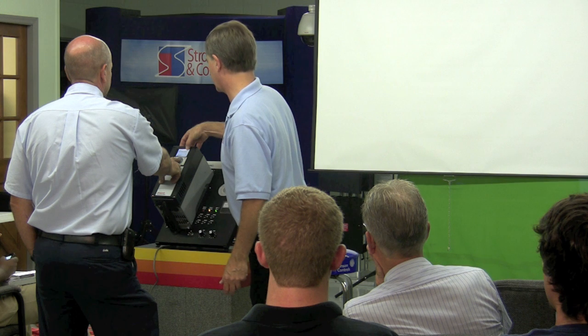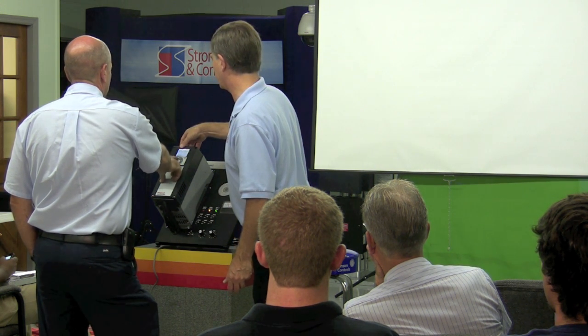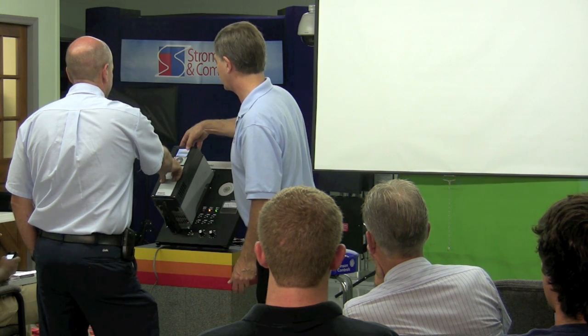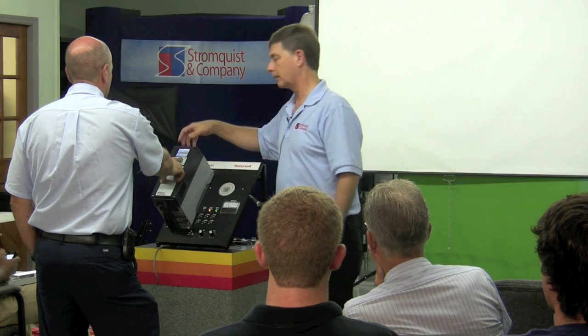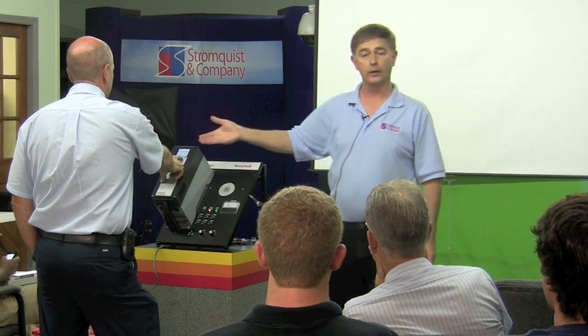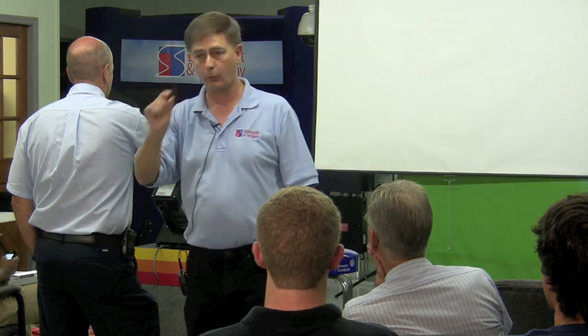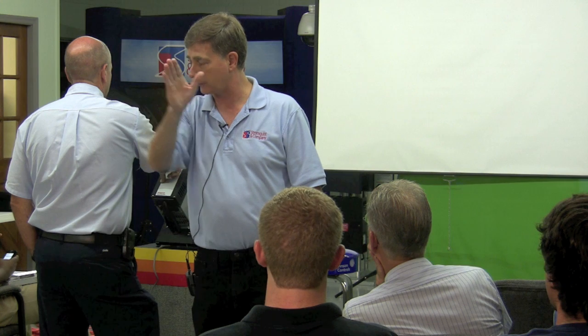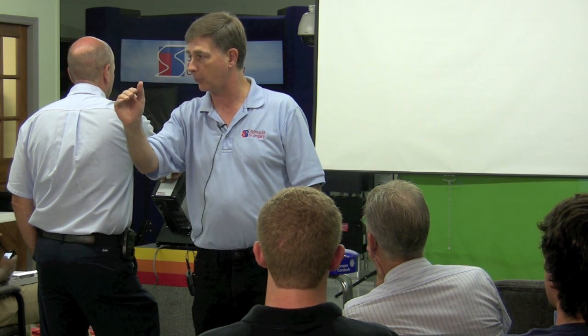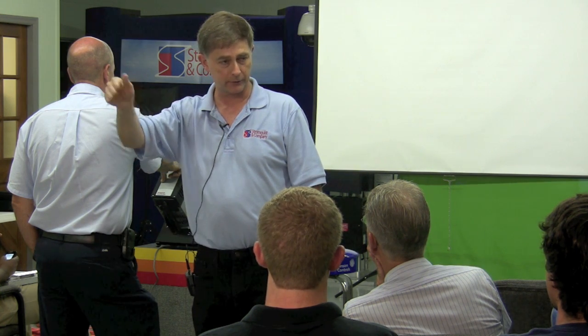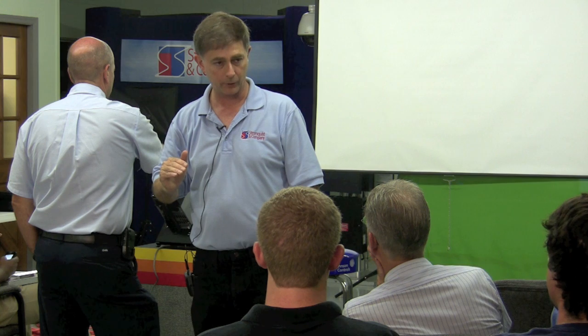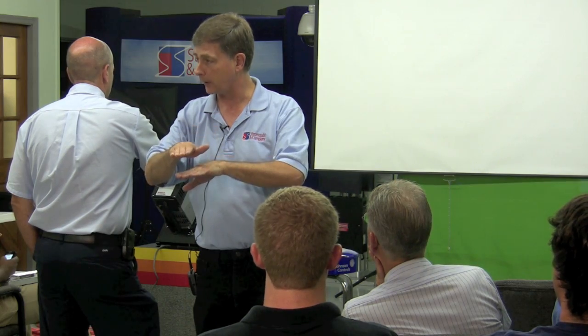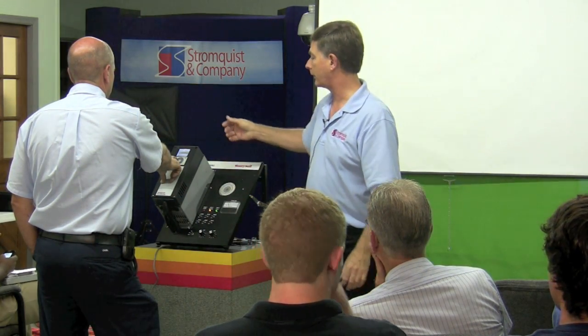So this is the low limit — hit enter. Back up to where you can go to the high limit, range one high limit. Edit, and then go above 24. And what he's done is he's effectively masked out the problem parameter. All he had to do is make sure he was at the beginning. He wanted to tweak a parameter, so he went to parameters. He wanted to mask out a frequency, so he'd scroll down within parameters to prohibit frequency, and went to high and low, put in the data — he's effectively masked out the frequency.